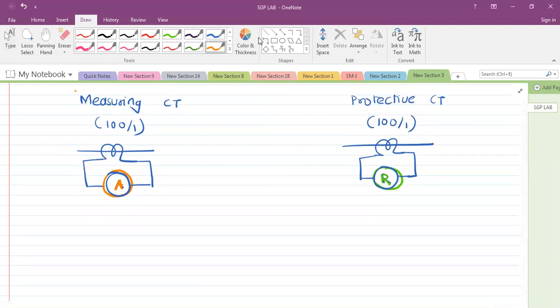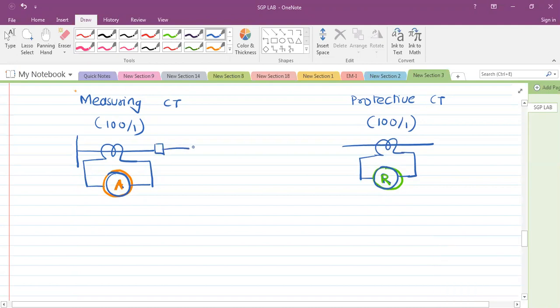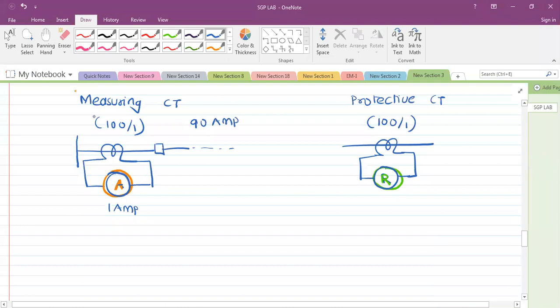Now here you have connected this meter. So this is a circuit breaker and here we have a transmission line. This is a measuring CT. So what is connected in series with the measuring CT? The secondary side meter. What will be the meter capacity? 1 ampere. Clear? So let's say the rated current of this line is 90 ampere and you have selected a 100/1 CT. So the maximum full load current is 90 ampere. So 0.9 ampere will flow through the meter on the secondary side at full load. So does the meter have any issue from no load to full load?